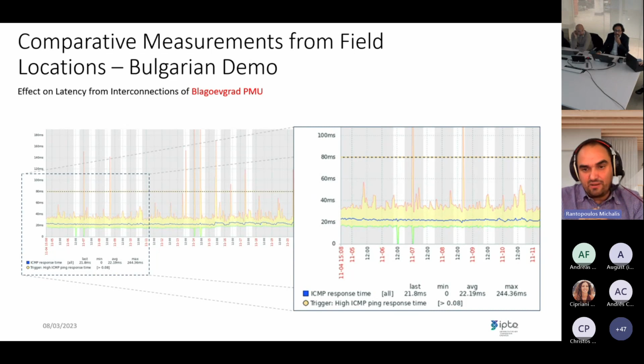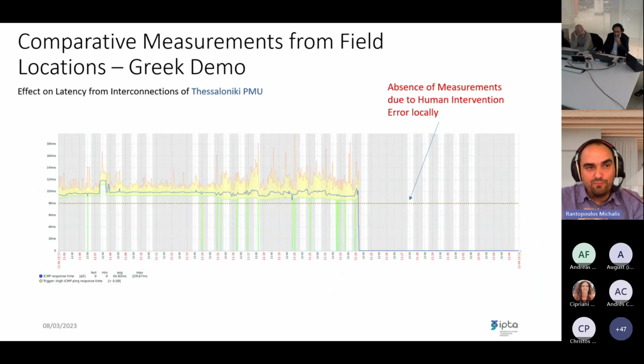However, when we move to the Greek demo, with the Thessaloniki PMU measurements broadcasted, we can see that the average value of the latency exceeds our criteria. We've performed investigations into where the majority of the excessive delay is focused, and this is due to the roaming interconnection—specifically the involvement, as we saw in the call flow path earlier, of the GRX interconnection path.